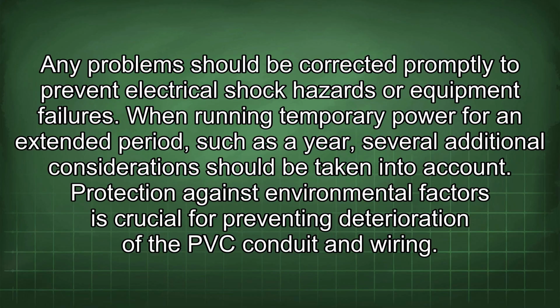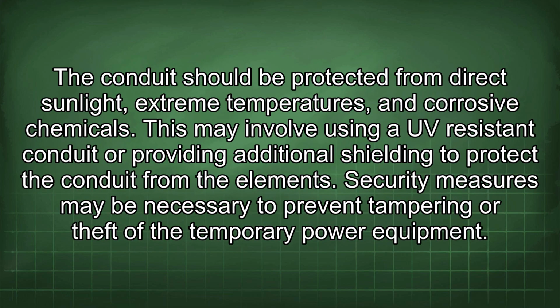When running temporary power for an extended period, such as a year, several additional considerations should be taken into account. Protection against environmental factors is crucial for preventing deterioration of the PVC conduit and wiring. The conduit should be protected from direct sunlight, extreme temperatures, and corrosive chemicals. This may involve using a UV-resistant conduit or providing additional shielding to protect the conduit from the elements.